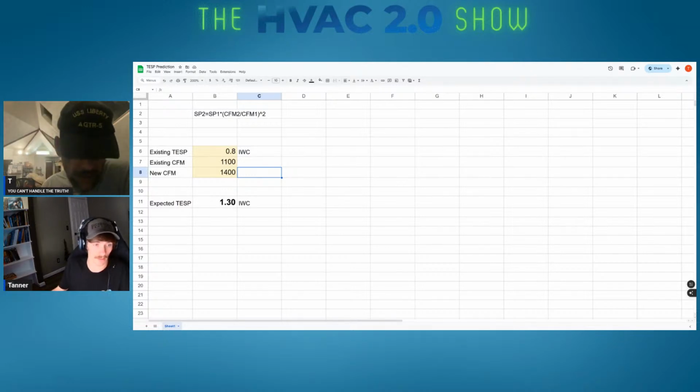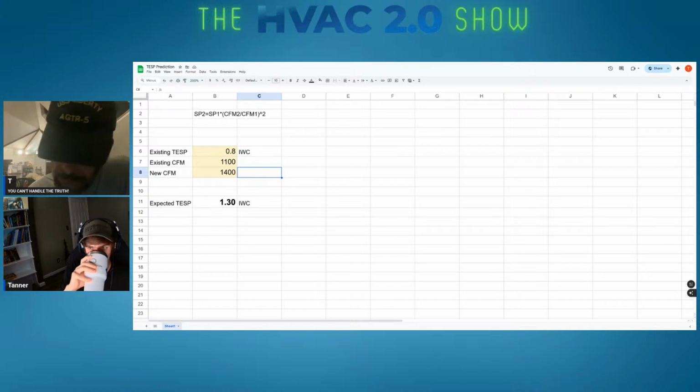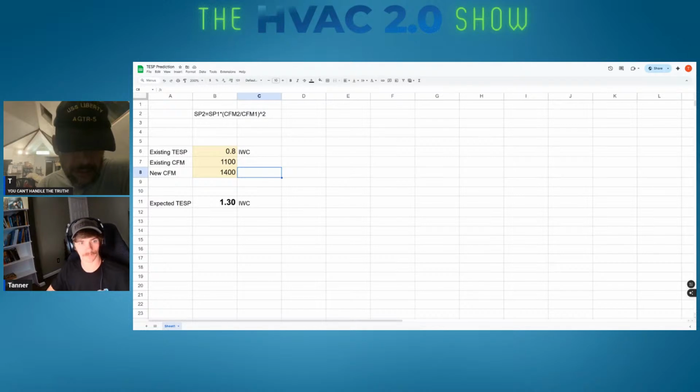I have an anecdotal story that Ronnie told me about one of his sales from last year. The homeowner called, unhappy about her energy bill. Ronnie said, well, that's kind of strange, and he took a look at the installed pictures, and they didn't put the equipment on the riser box he specified. So the energy was going up because that ECM was throttling up during the heating season, and a lot of extra energy went to the fan.